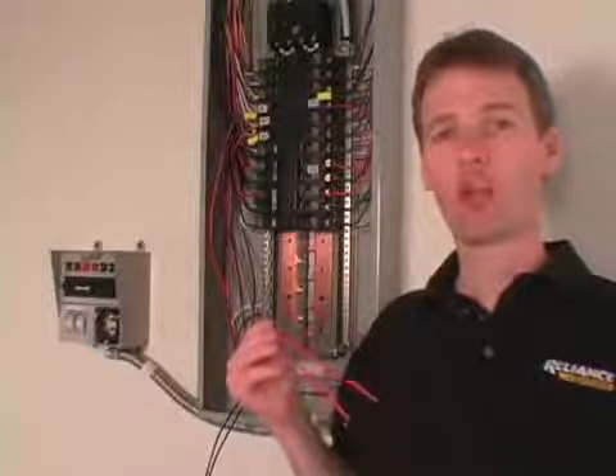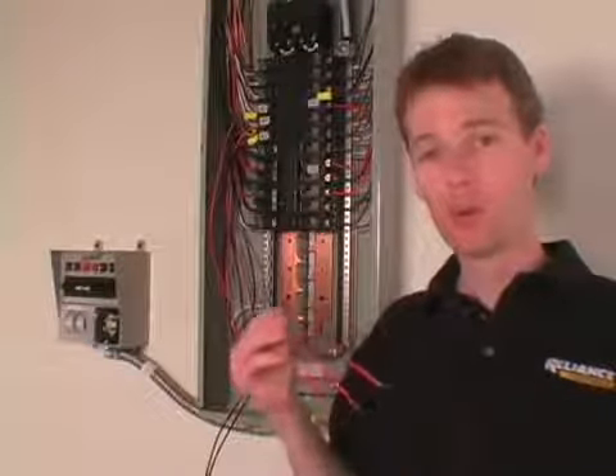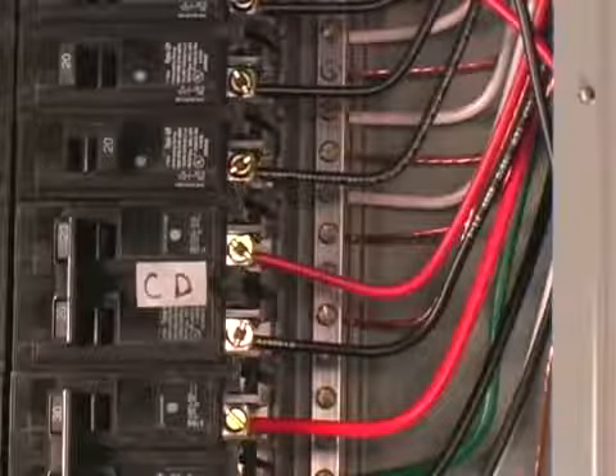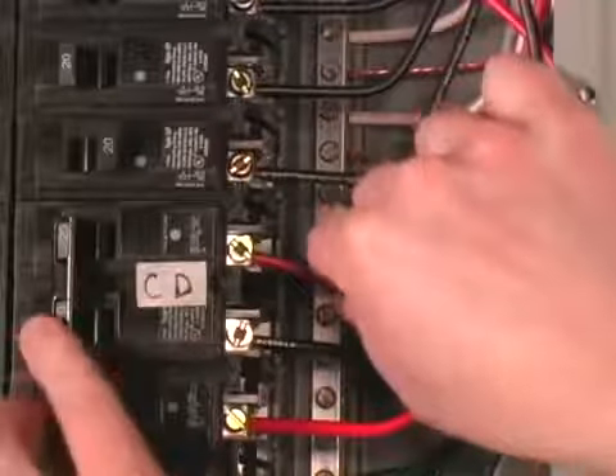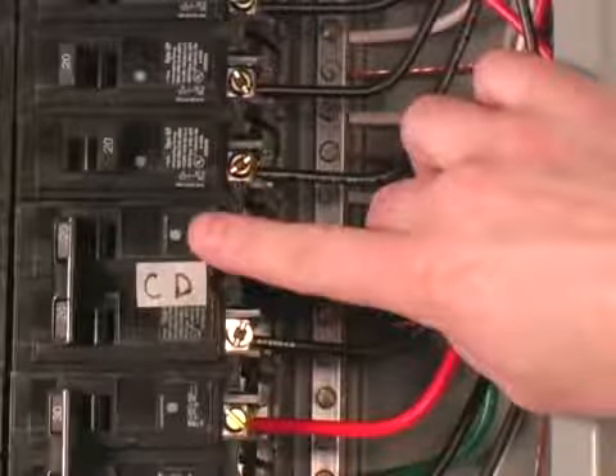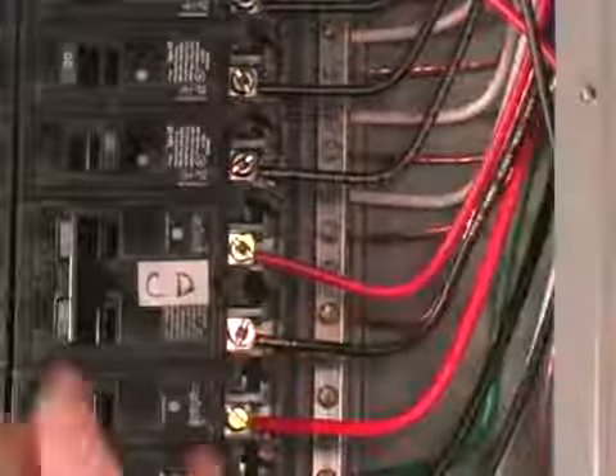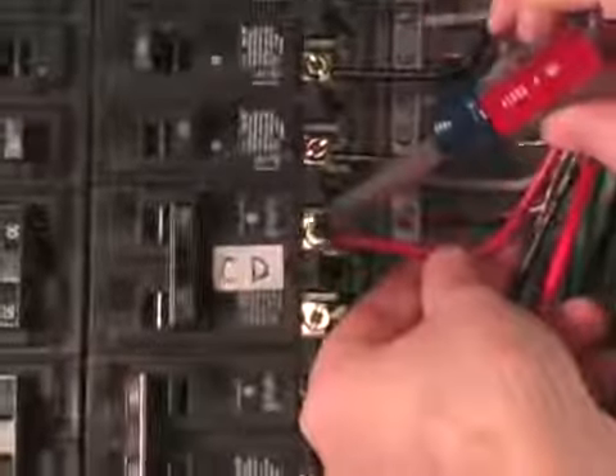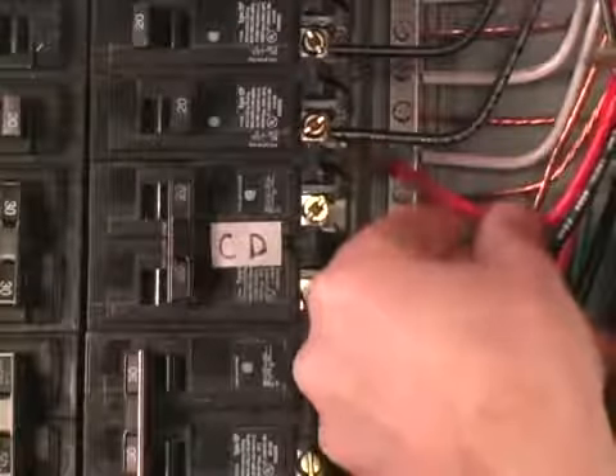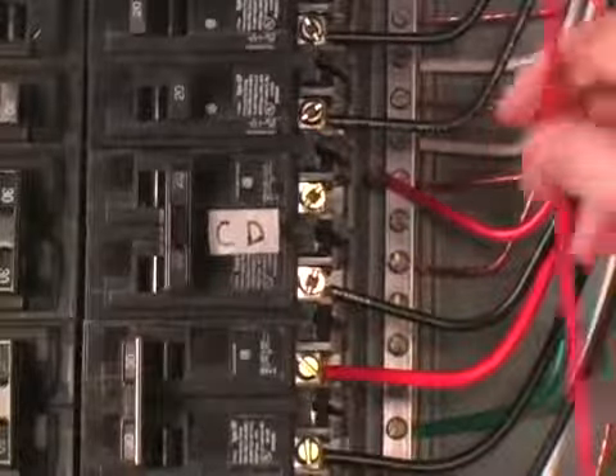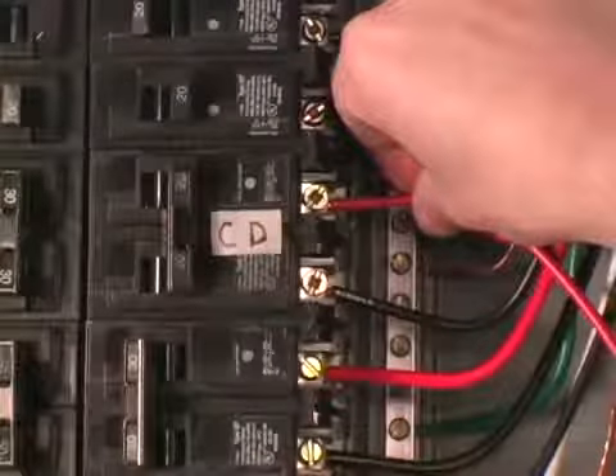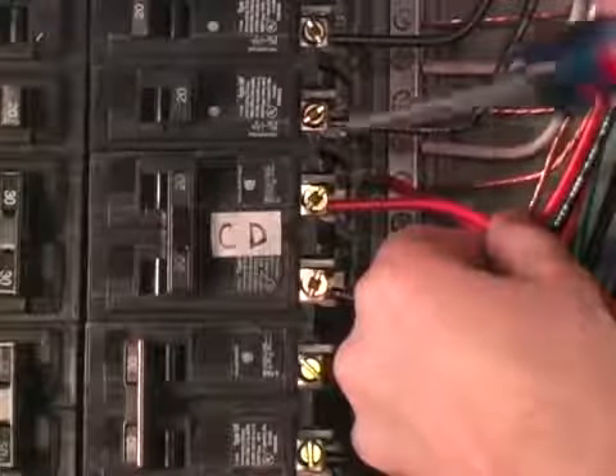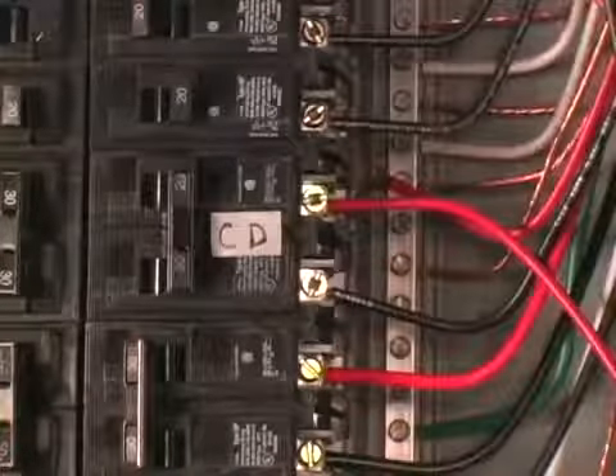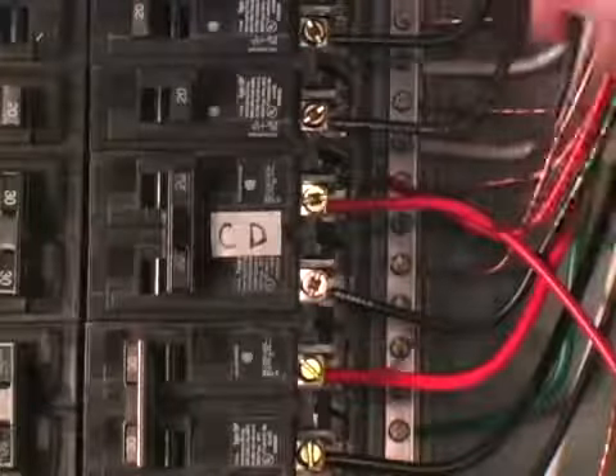Because our 240 volt well pump is on a double pole circuit breaker, we'll need both the C and D circuits from the transfer switch. Installation is the same as the 120 volt single pole circuits, except that we'll connect the C wires to one half of the double pole breaker and the D wires to the other half. Turn off the breaker, remove the wire, take the red wire labeled C and put it in one half of the breaker. Take the black wire labeled C and tie it to the wire that was in that side of the breaker.